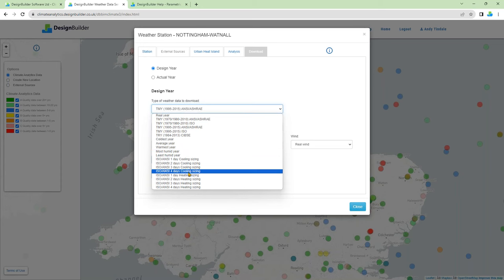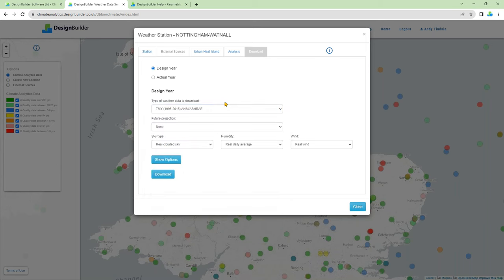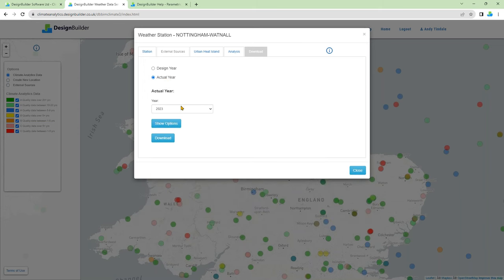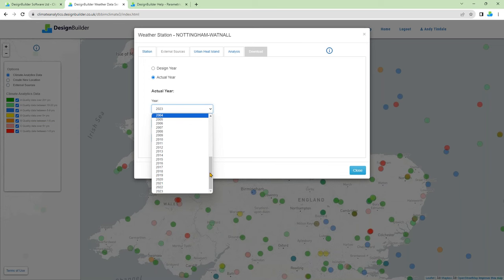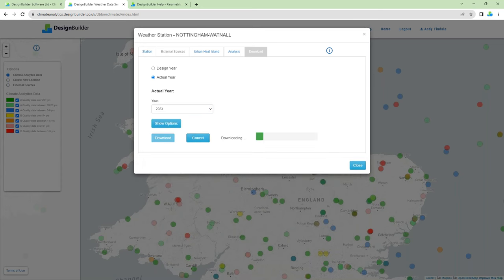Now we'll look at actual year data. For actual years you can simply select the year, although there are some other more advanced settings. Actual year data is based on hourly values from a dense grid of data points from the NASA hourly database. These weather files contain actual data for a specific location and a specific year. Actual year data is available for all stations from 1980 right up to the previous month of the current year. To illustrate, I'll download 2023 data for Nottingham and load it into the Design Builder Results Viewer.